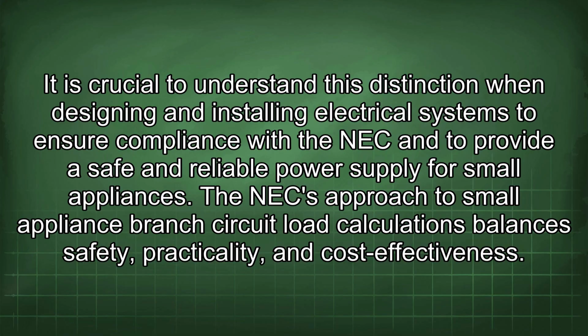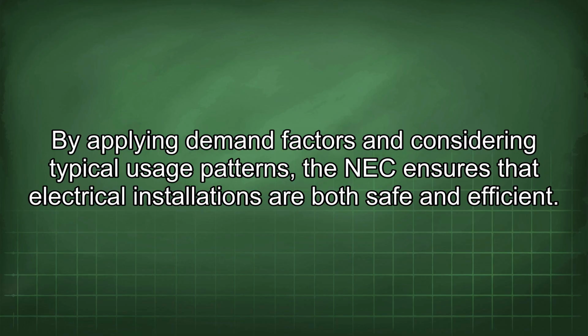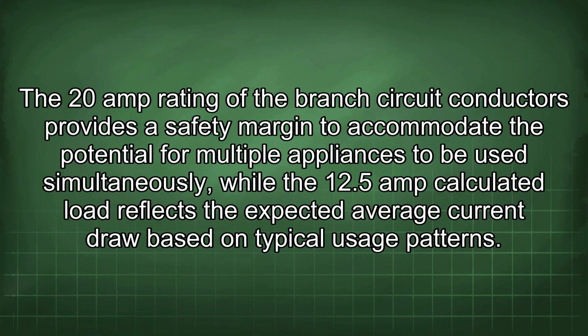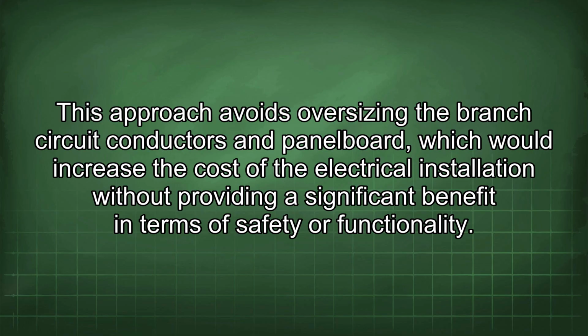The NEC approach to small appliance branch circuit load calculations balances safety, practicality, and cost-effectiveness. By applying demand factors and considering typical usage patterns, the NEC ensures that electrical installations are both safe and efficient. The 20 amp rating of the branch circuit conductors provides a safety margin to accommodate the potential for multiple appliances to be used simultaneously, while the 12.5 amp calculated load reflects the expected average current draw based on typical usage patterns. This approach avoids oversizing the branch circuit conductors and panel board, which would increase the cost of the electrical installation without providing a significant benefit in terms of safety or functionality.